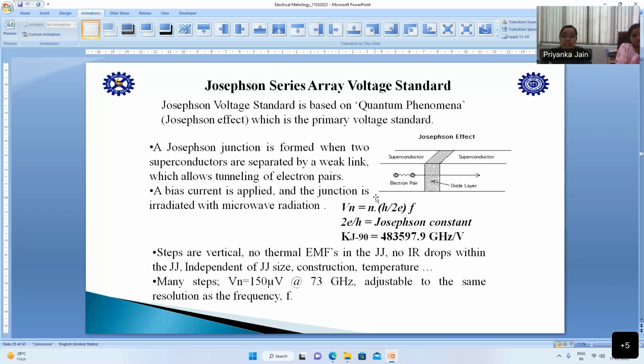This Josephson junction is ideally considered independent of construction, size, and temperature. There is no noise and no thermal EMF in the Josephson junction. There is no IR drop, that means voltage drop, at all, because the steps are vertical, the alignment of these junctions is vertical, so there is no chance of voltage drop or thermal EMF. So we can have a stack of junctions which can generate many voltage steps. For example, if we give 73 GHz of frequency to the Josephson junction, we can generate 150 microvolt. Based on the frequency, we can adjust the voltage from a lower level to a higher level.